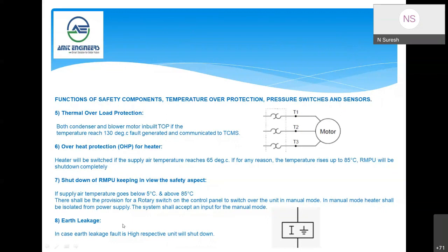Thank you. So we are discussing the overheat protections. One is at the motor level and the other for the heaters. In the heater, there are 3 levels of protection: 65 degrees Celsius, 85 degrees Celsius, as well as 130 degrees Celsius. And other than this, we give the earth leakage protection. This is again mounted in the switchboard cabinet, which is supplied by Meda.